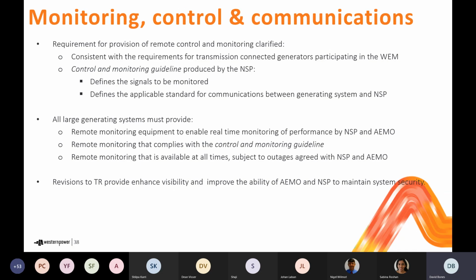The last set of technical requirements specifically related to large generating systems deal with monitoring, control and communication requirements. Again, we've sought to align the requirements for large generators as expressed in the technical rules with those in the WEM rules. We've removed from the technical rules a list of quantities that used to be there around the signals to be monitored and controlled. Instead, we've introduced a requirement for Western Power to produce a control and monitoring guideline. That guideline will provide information, including the signals to be monitored and the applicable communication standard that needs to be adhered to for the communication systems that take those control and monitoring signals from the generator back to the network service provider.